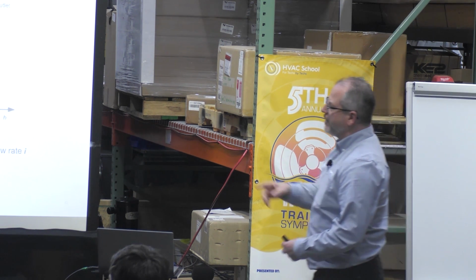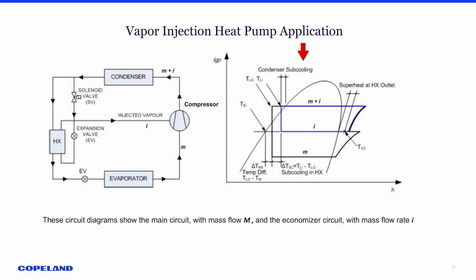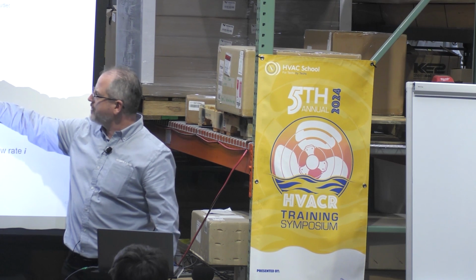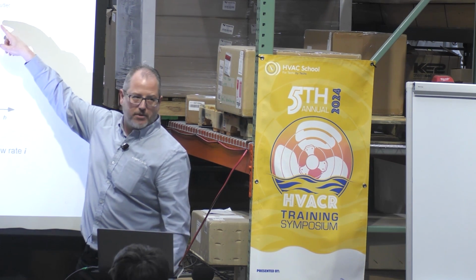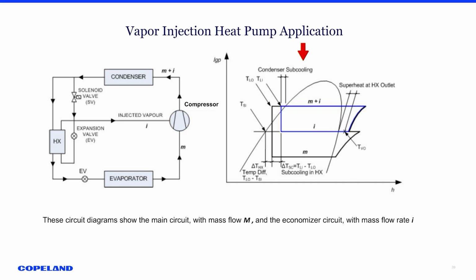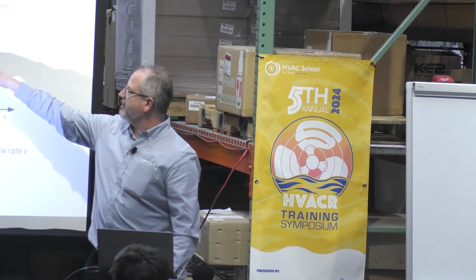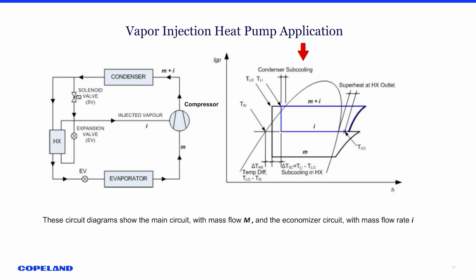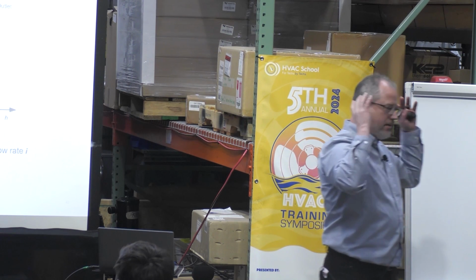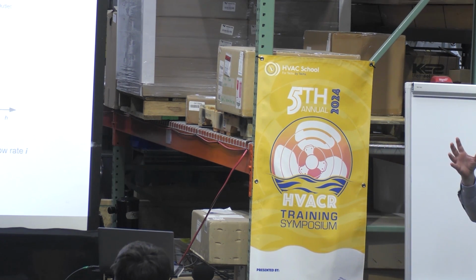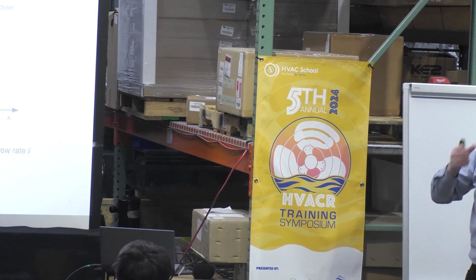So when we look over here, our compression cycle follows the lines of entropy on our pressure enthalpy diagram. And normally on a system, if we're starting off right here for temperature, our discharge would follow that line of entropy, and our temperature would be way over here, and it'd be very hot, right? When we have injection, we are injecting into the middle of that scroll set. All of a sudden, look at our temperature go down instantly. Now we have a lower temperature. On the pressure enthalpy diagram, we were just looking at a snapshot of that system, right? So we can really see how that cools down that compressor.